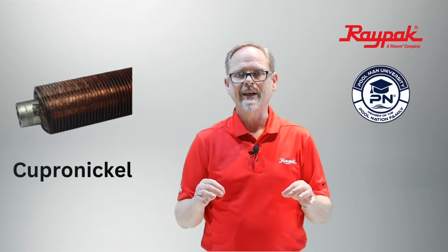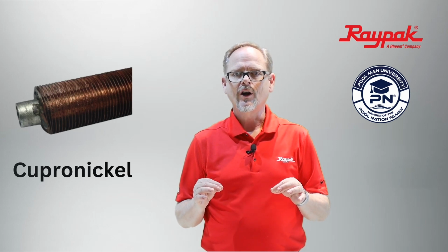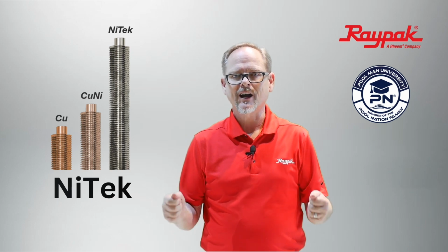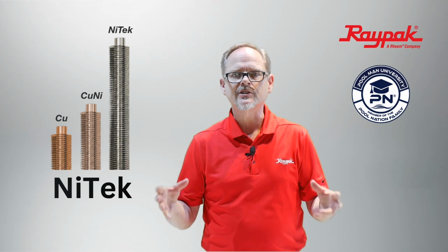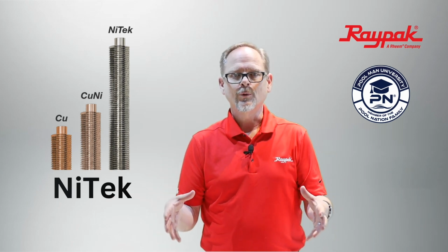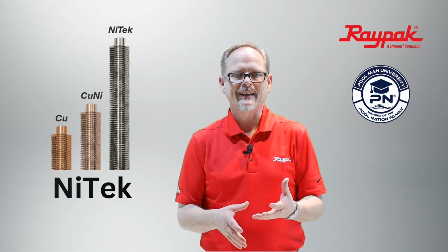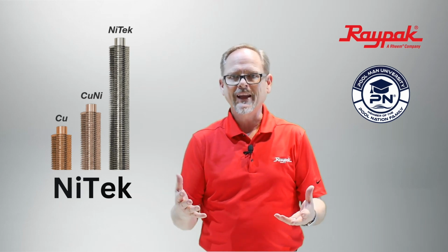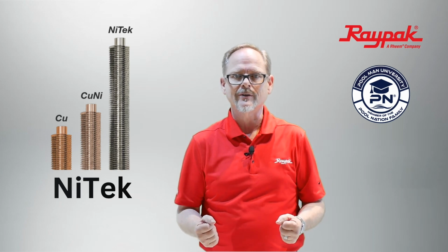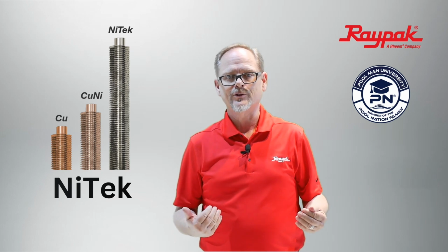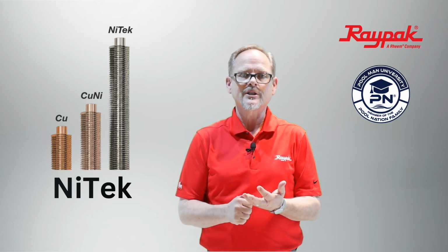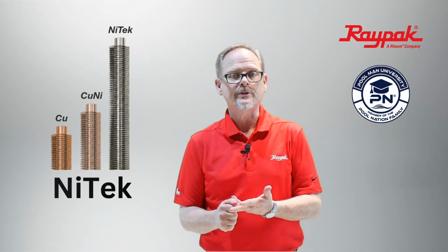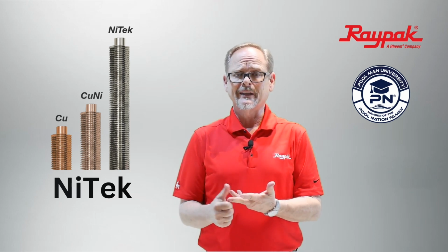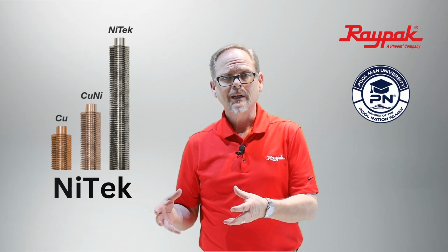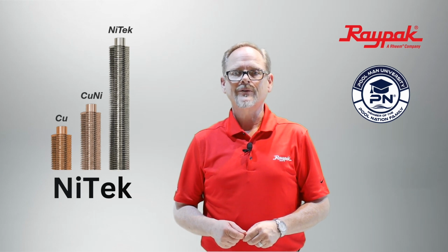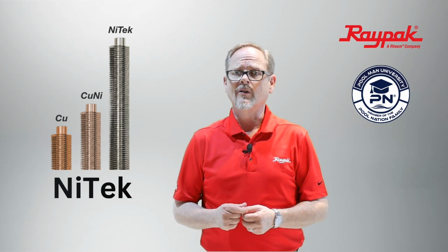What if, instead of putting that nickel in the copper, we put it on the copper? We coat the entire heat exchanger in the tubes, outside the tubes, the fins, the tube sheets, everything is coated with nickel. Okay. This, we found, gives us 900% more nickel, in the areas that are critical where the water makes contact with the heat exchanger. It also makes it more efficient. It gives you that 2% efficiency back. So we're 300% more corrosion resistant than standard copper, 200% more erosion resistant than cupronickel, and 50% less likely to form scale inside the tubes, simply because it's too slick for the scale to grab onto. This is something that's not available on any other product on the market.